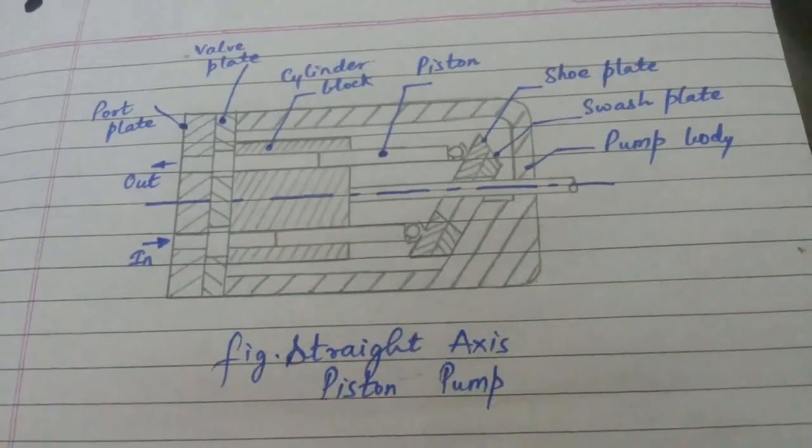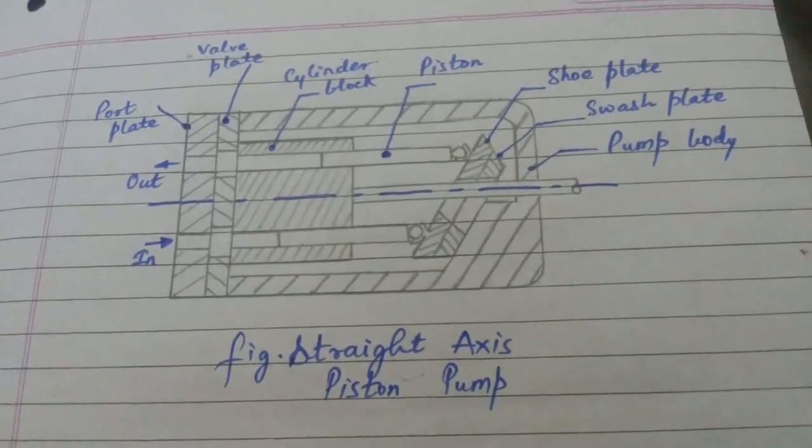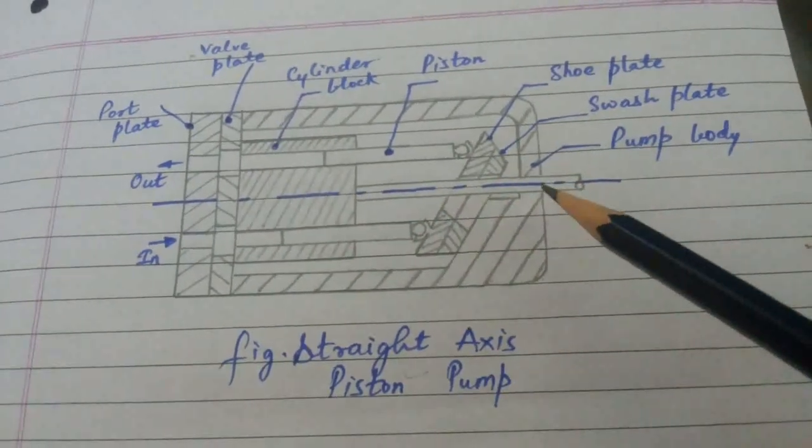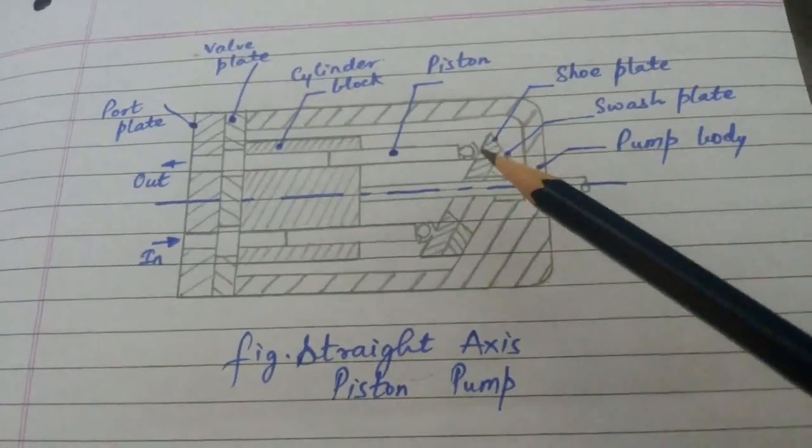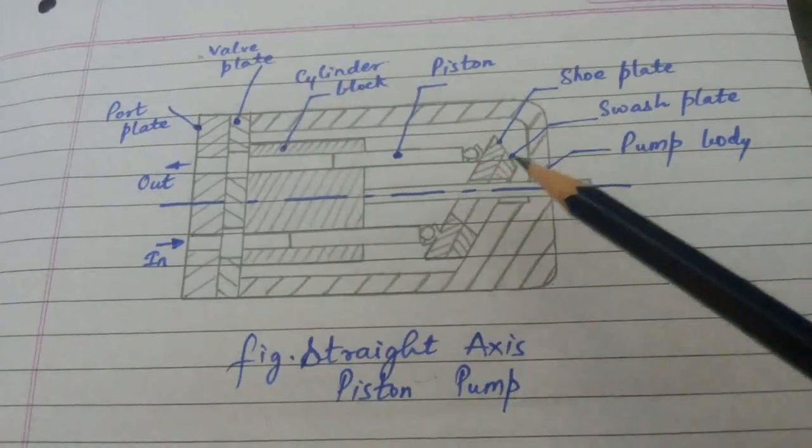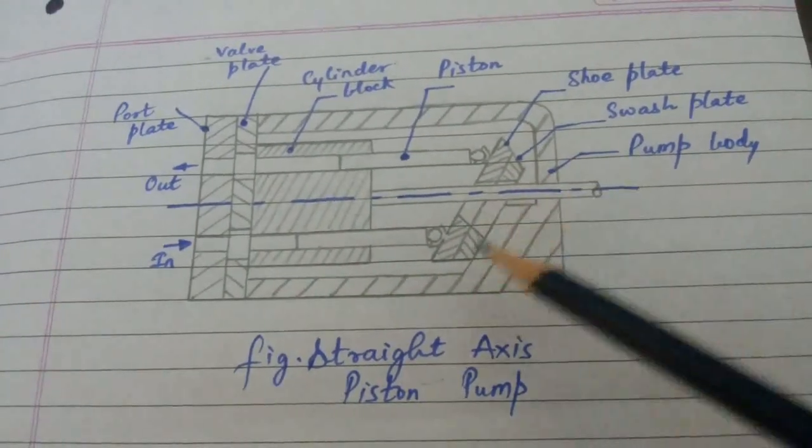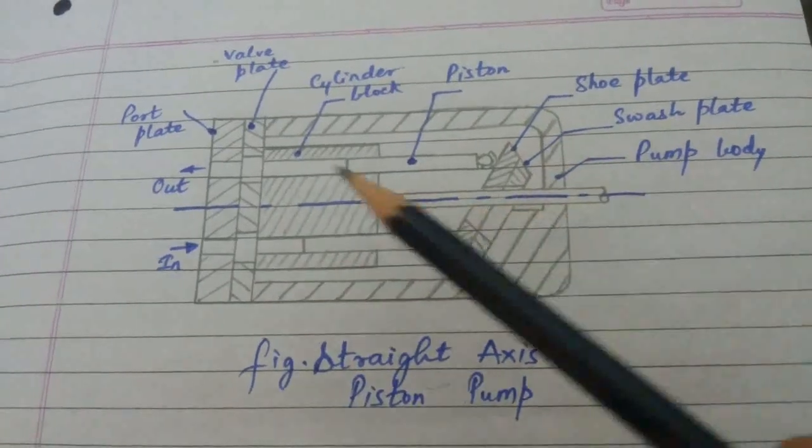So in the straight axis piston pump, the cylindrical block is fitted with the drive shaft. The shoe plate is mounted on the swash plate which is fixed at an angle to the axis of rotation.